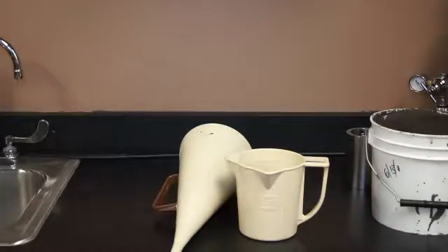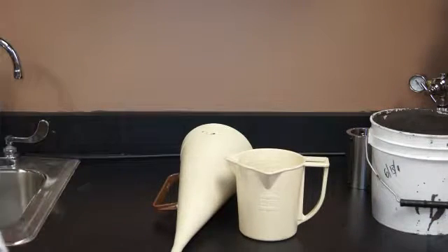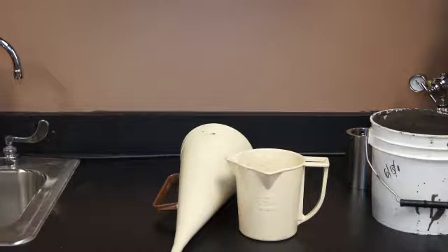And typically, kinematic viscosity is, if you do the formulation, it's the centipoise reading divided by specific gravity. So you get into density considerations there, which you don't really consider when you're doing, or you don't consider so much when you're doing a regular rheometer, a couette style with a rotating rotor and a bob attached to a bob shaft.